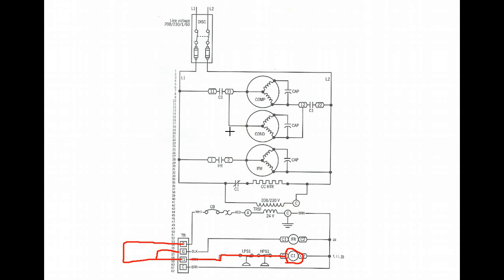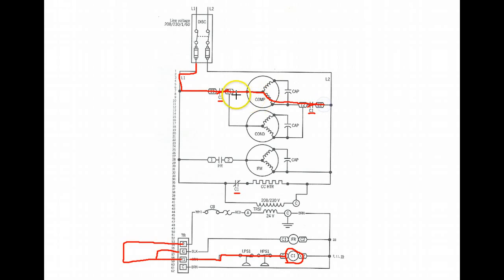Now go up to the high voltage side of the circuit and look for the C1 contacts. These three contacts are at rest with no call for cooling and the contactor de-energized. When 24 volts is applied to the C1 solenoid, the normally open contacts close, allowing current to flow through the compressor and applying voltage to the condenser fan — so they will be running. The normally closed contact opens up, removing power from the crankcase heater, so the crankcase heater is turned off.